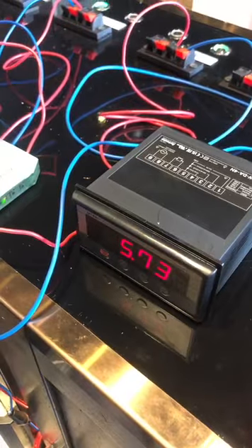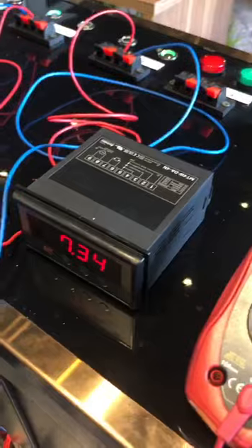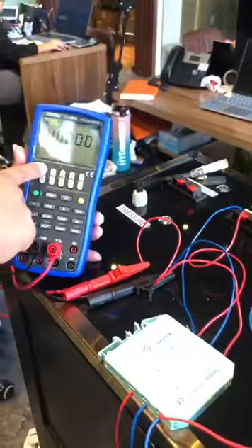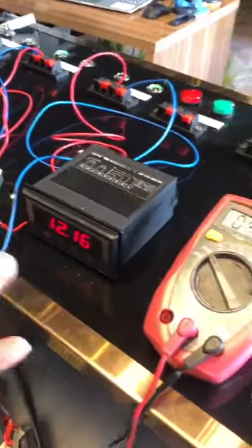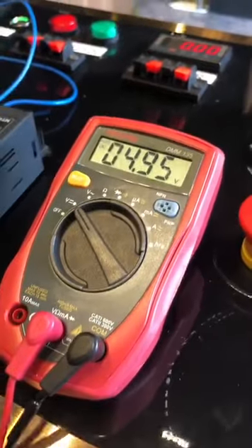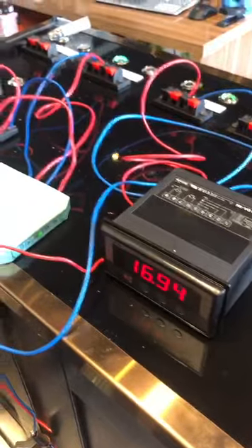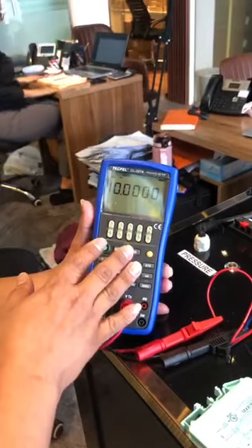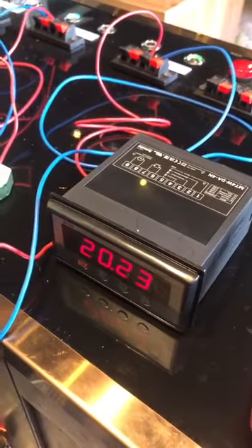If I start to increase until 2 volts, you will notice that the value is also increasing from our outputs. 3 volts, increasing, 4 volts, and here is the 5 volts. So we can see our output modules, or output devices, are responding accordingly, meaning this device is giving us the correct signal. Up to 10, we should expect half of the output at 5. When we reach 10, this is full 100%.